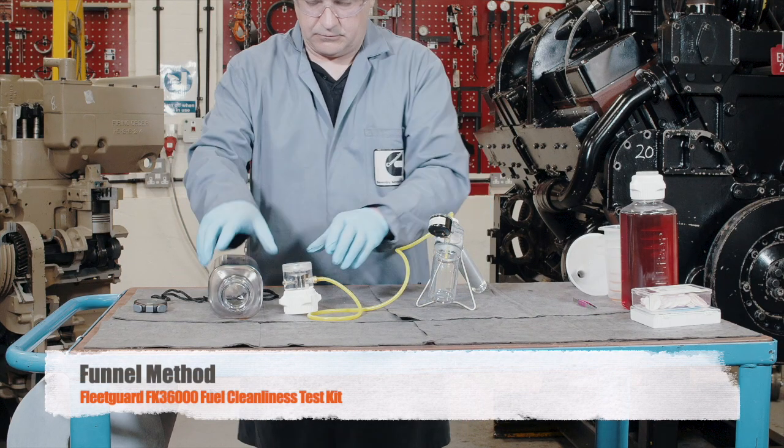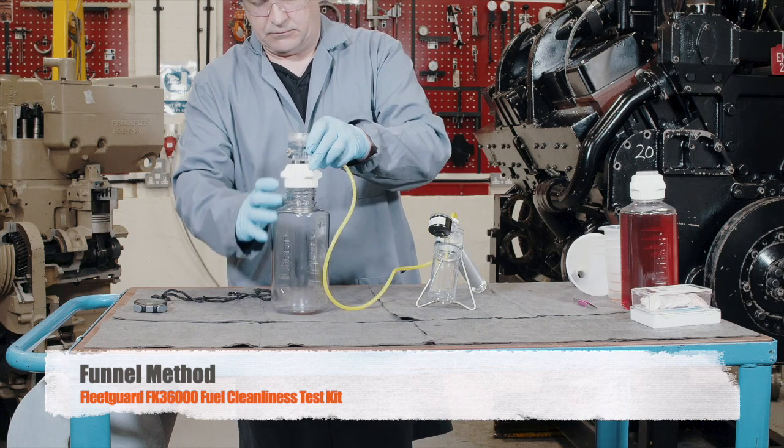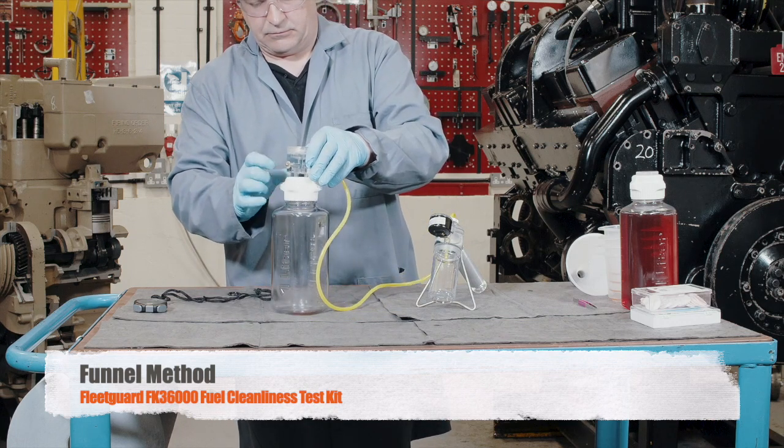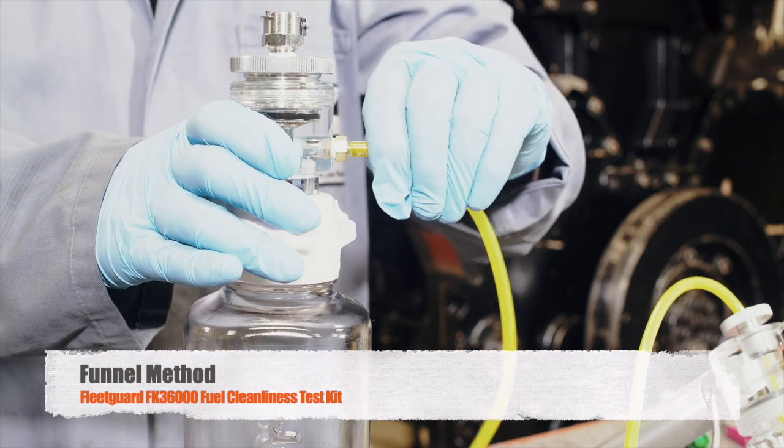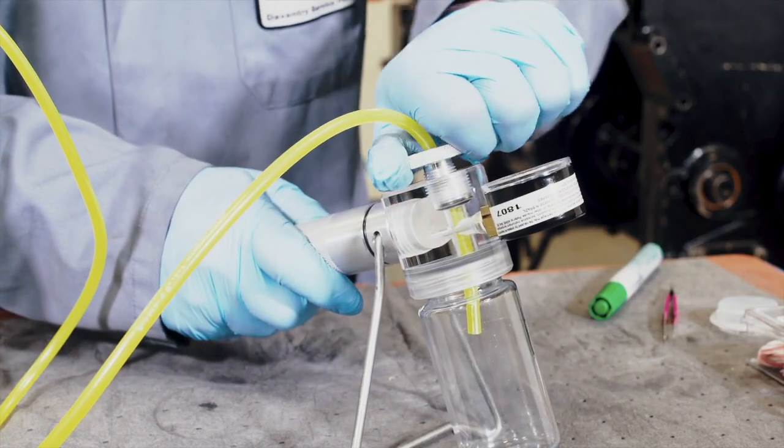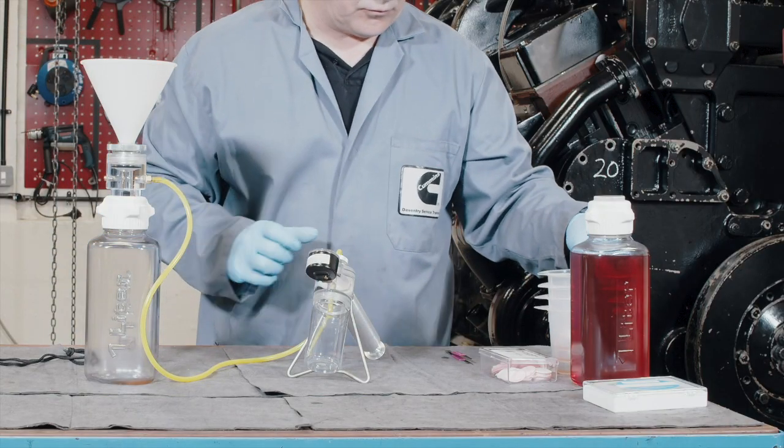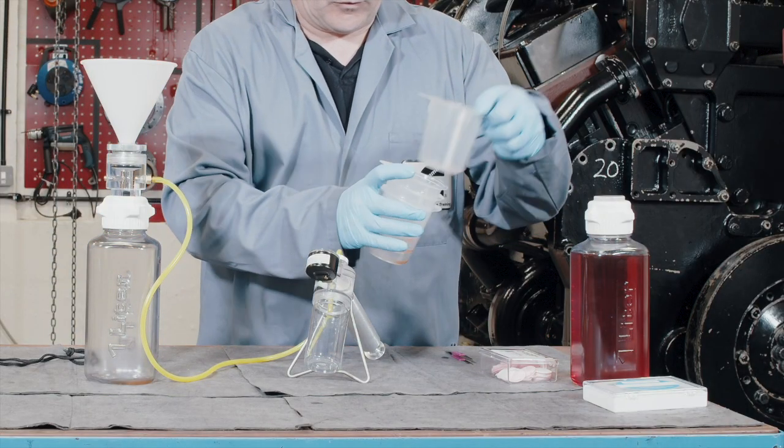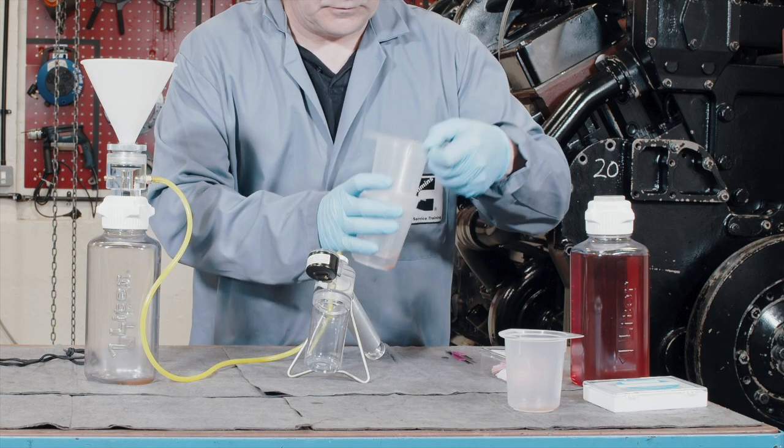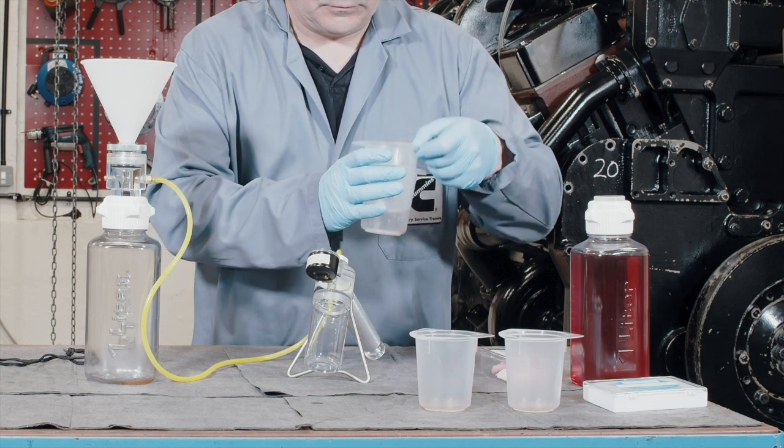Start by assembling the equipment in accordance with the instructions provided, ensuring that the vacuum hose is securely fitted to the vacuum adapter and that the aluminium collar on the vacuum pump is tight. The funnel test method measures the time of flow of four 250 millilitre samples of fuel through a selected filter media patch.